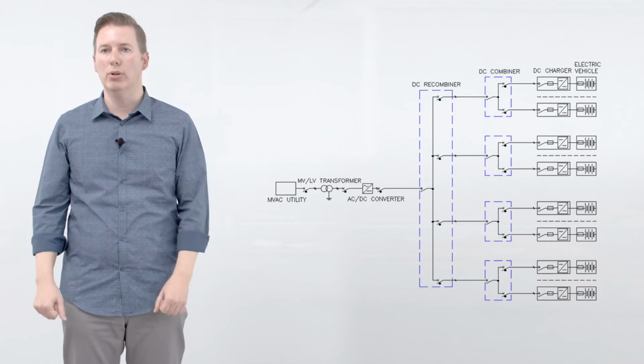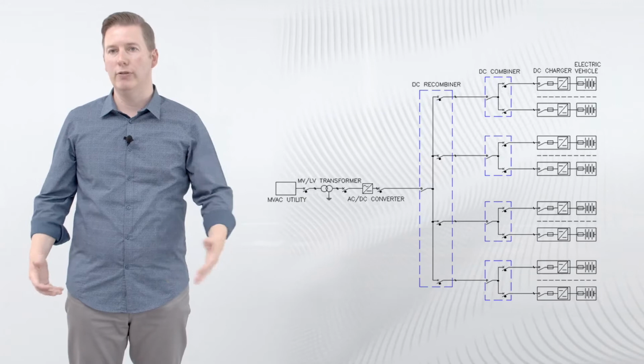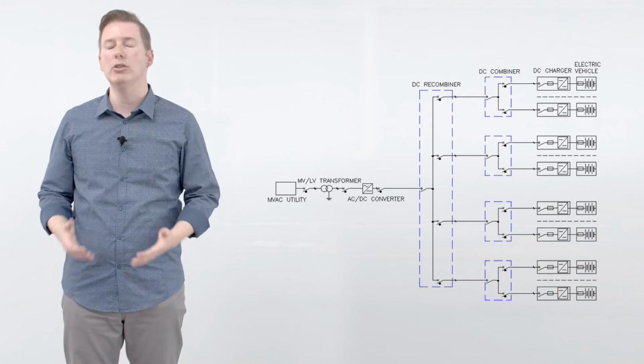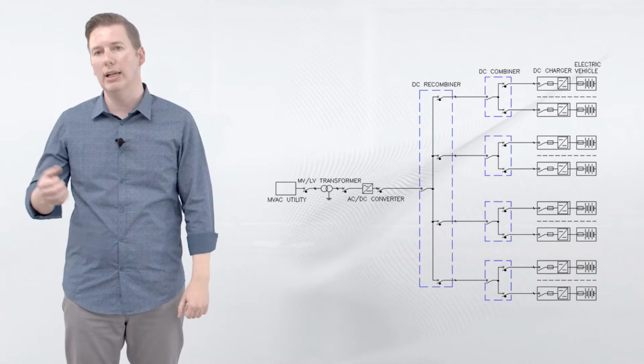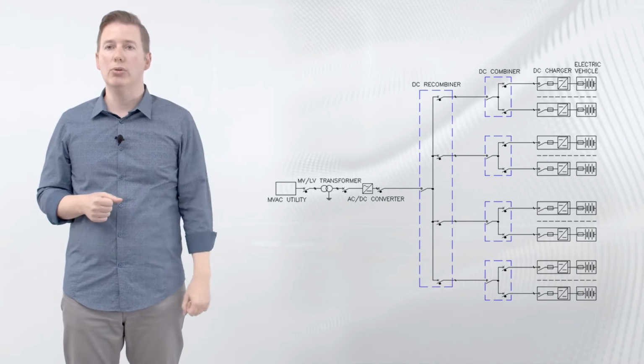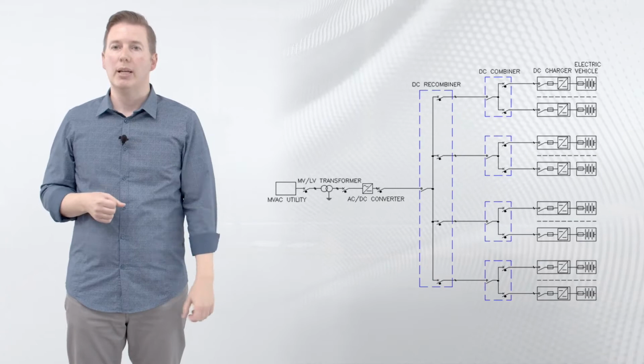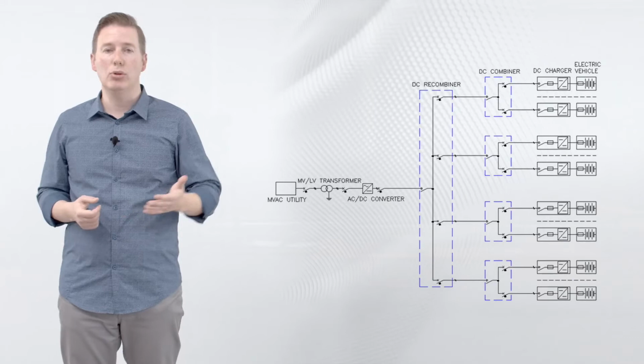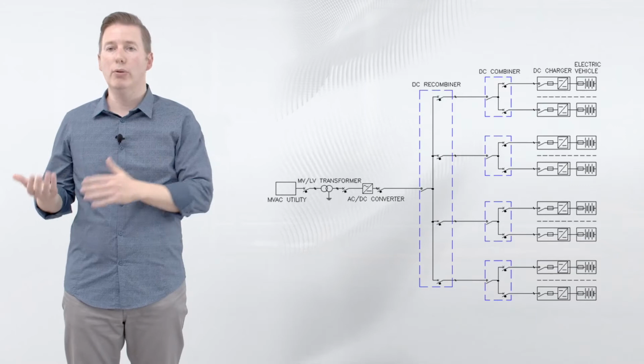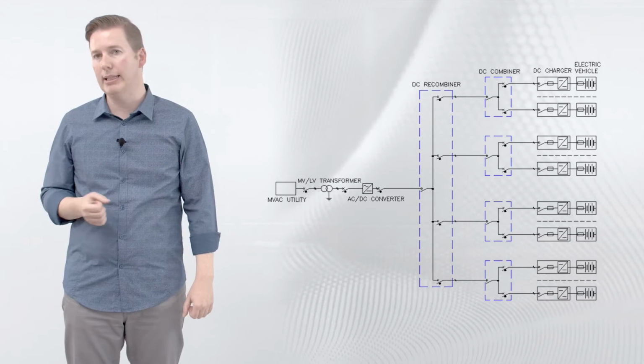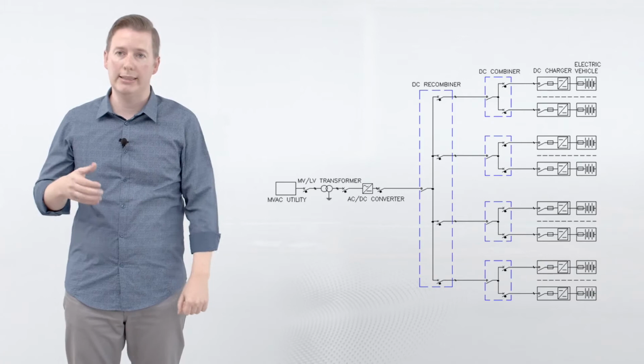Then we have a DC charger, one for each electric vehicle, in which we have a DC-DC converter in order to adjust the DC voltage and to control the charging phase. In addition, we have the relevant fuse and switch disconnector to protect and switch. Then, according to the nominal power of the plant and to connect all the DC chargers in parallel, we can have both the so-called DC combiners and the DC recombiner with the relevant circuit breaker and switch disconnector inside.